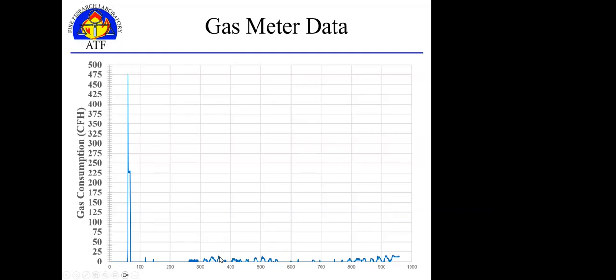That occupant messed with the meter or a gas line, it jumped up to say 100 cubic feet per hour, and it sat there, and then the house didn't blow up. So then that occupant went and messed with the gas line again, and it jumped up to 200. And then it sat like that for an hour and still didn't blow up the house. So they went and messed with it again, and it jumped up again, and eventually it did blow up. But you can see how they went back repeatedly and started monkeying with that gas line.